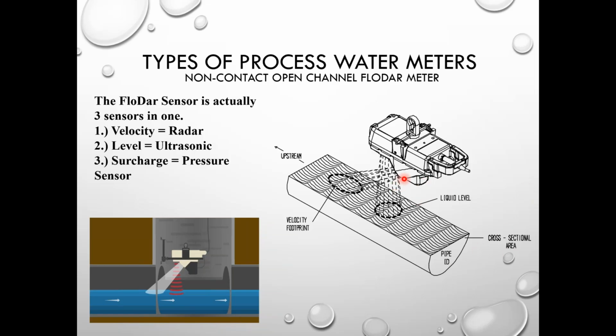So the radar beam shoots downward and outward, and it reflects off particles, disturbances off the surface, causing a frequency shift. The return signal is compared to the frequency of the transmitted signal, and that's called the Doppler frequency, directly proportional to the velocity of the flow. With this type of flow meter, they've actually run it through various different size pipes. So it also has what they call an algorithm for the velocity. So it's reading the surface velocity, but it's able to correlate an average velocity based upon tests that they've done at the factory.